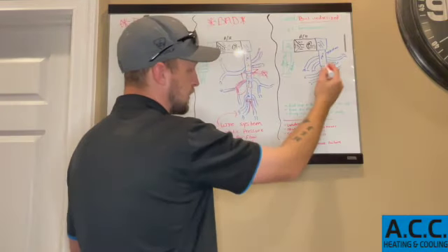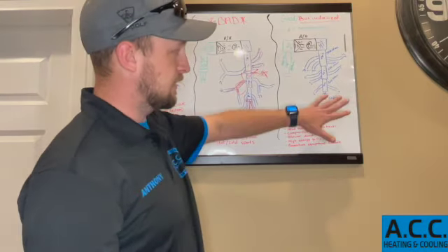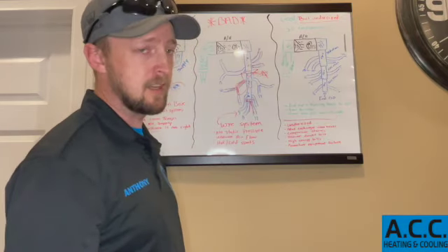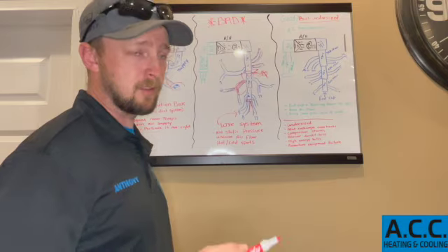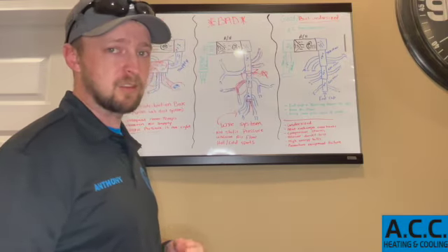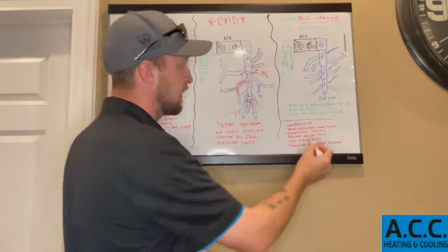We go over here to this one. I built this duct system the correct way. Everything on it is the way that it's supposed to be, but it's undersized, and that's a huge problem here in the upstate. Everywhere we go, over half of our customers have undersized duct systems, and they don't even know it until we get there and see everything.